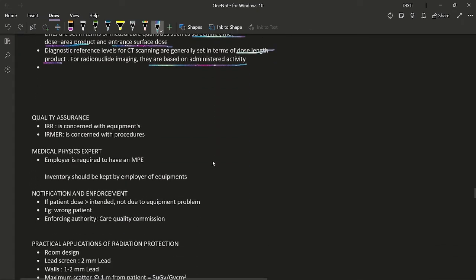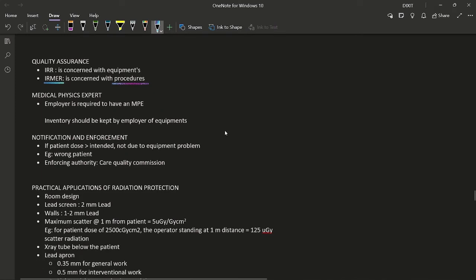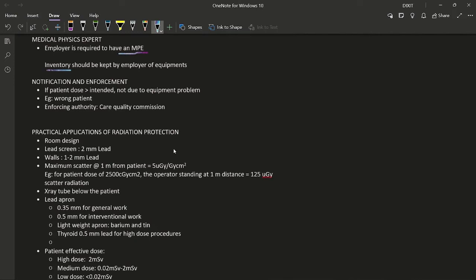Quality assurance (QA) can concern both equipment and procedures. Equipment QA falls under IRR, while QA of daily procedures falls under IRMER. According to IRMER, the employer must appoint a medical physics expert and maintain an inventory of all radiological equipment. Under IRMER, notification is required if the patient dose is much greater than intended but not due to an equipment fault (e.g., a wrong patient being irradiated). The enforcing authority for IRMER is the Care Quality Commission.